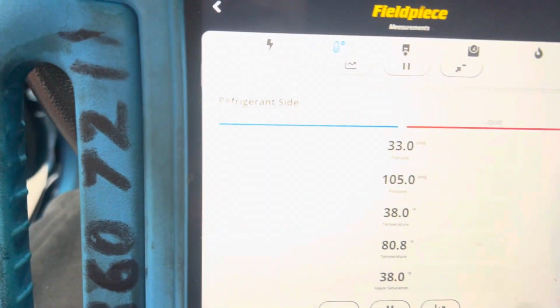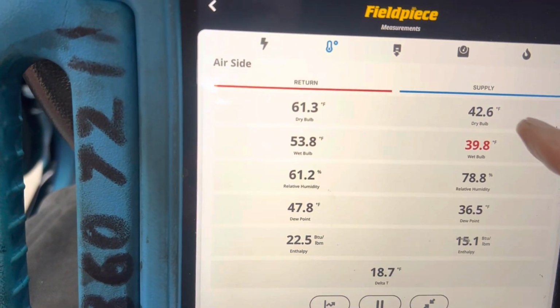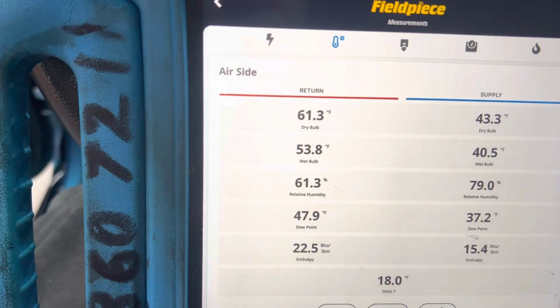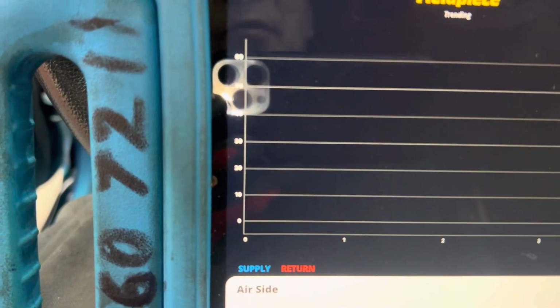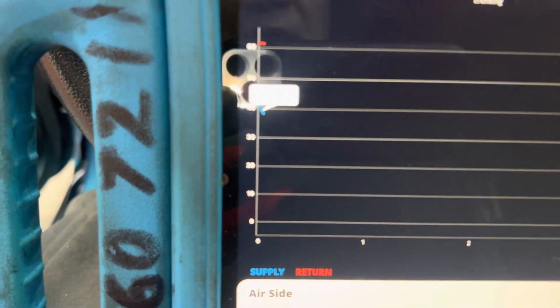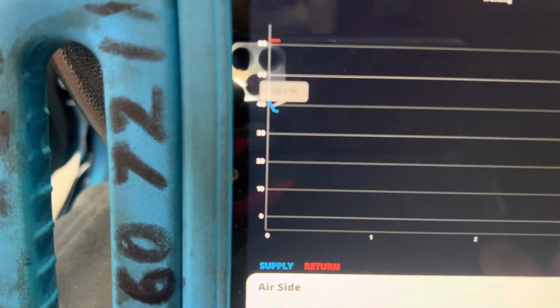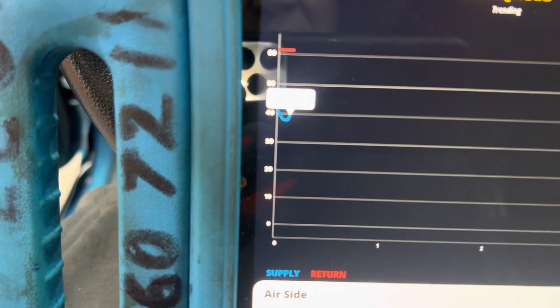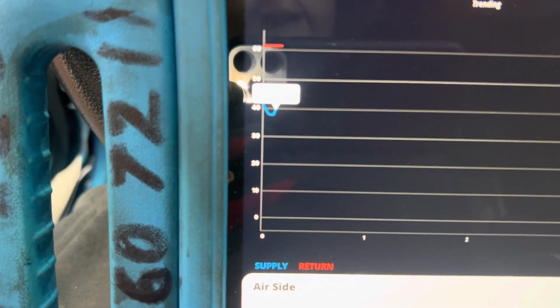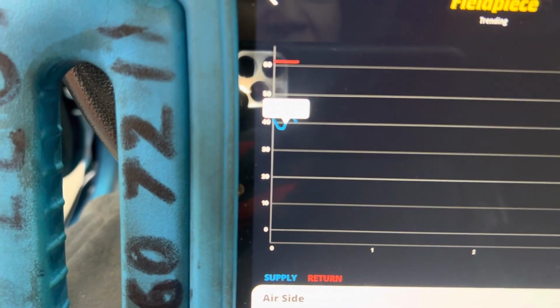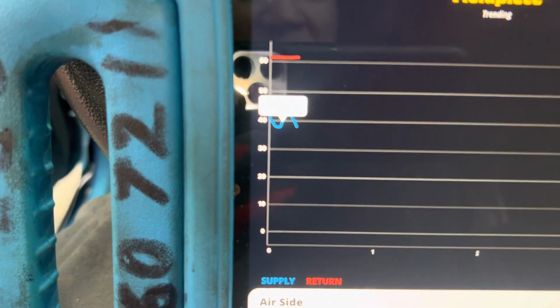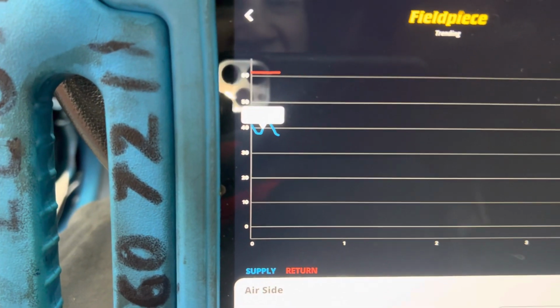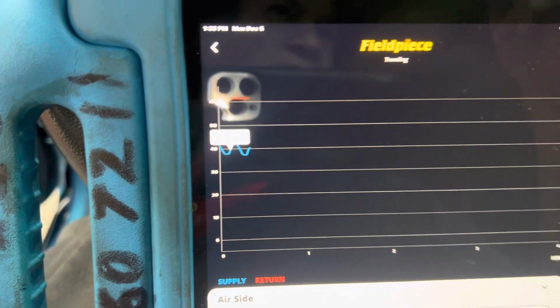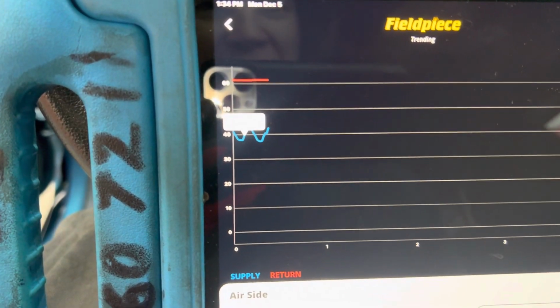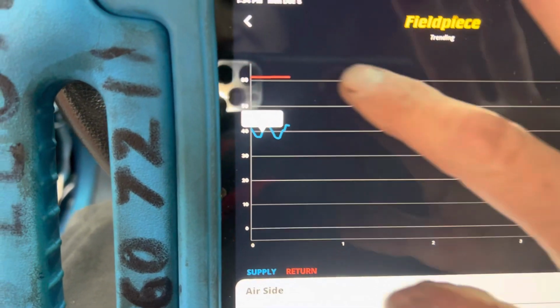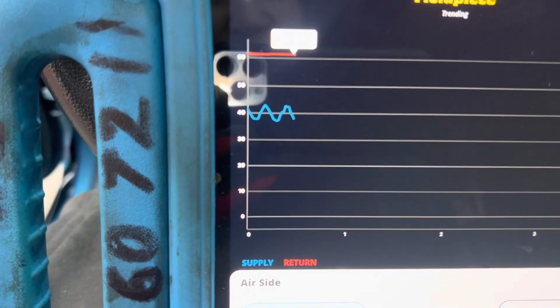Let me go back and look at our superheat, subcooling, and pressure, then our temperatures. Right there, let's see where we're sitting at, 39 degrees. It looks like it's going to hover right around 39 to 40 degrees, cycling. We're going to let this go for 5 or 10 minutes and let it stabilize. Let's look at our outside temperature, 61 degrees, that's ambient.